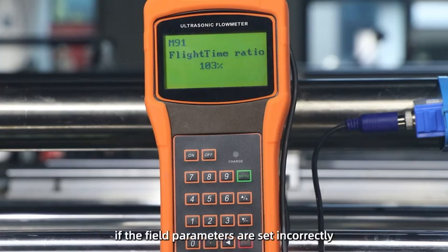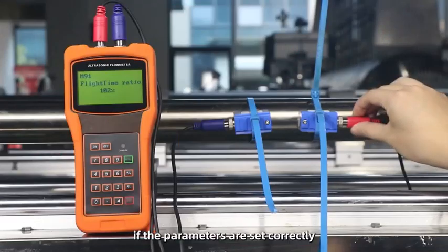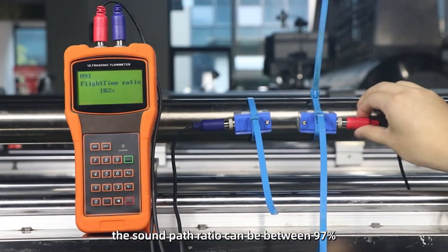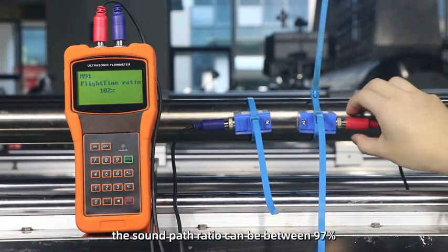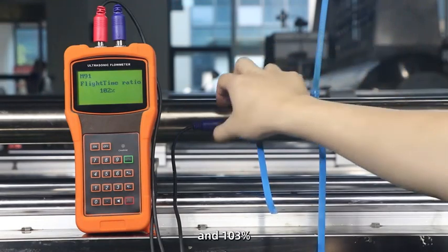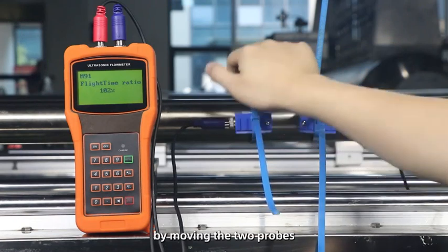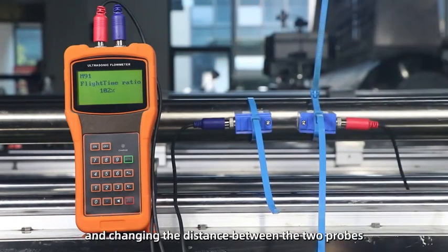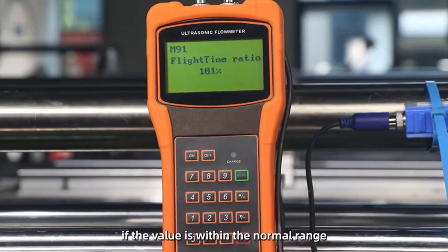If the field parameters are set incorrectly, the correct parameters should be re-entered before installation. If the parameters are set correctly, the sound path ratio can be between 97% and 103% by moving the two probes and changing the distance between the two probes. If the value is within the normal range, it means that the installation is correct.